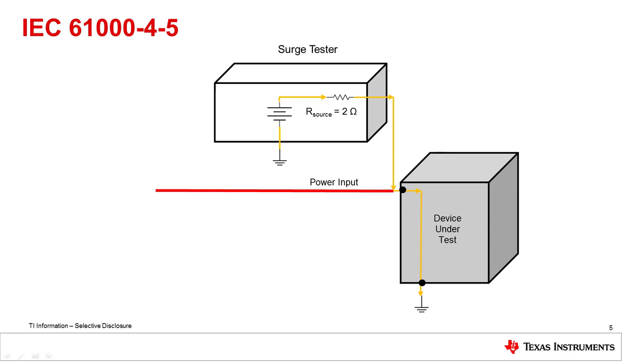When tested on a system, this waveform is applied with a peak voltage that typically ranges from 500 volts up to 4000 volts. This magnitude is approximated by the risks of the environmental factors discussed in part 1 of this video series. For example, a hot plug might be approximated as a 500 volt surge, while a motor kickback might be approximated at 4000 volts. This means peak currents of 250 amps and 2000 amps respectively, based on the 2 ohm output impedance.